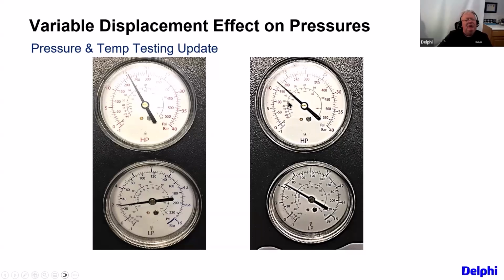In this case, it's because the compressor was put into a lower displacement mode. So normal duty cycle on the right, and high duty cycle on the left. That's why that went higher and the low side went lower. Then when we went to a normal duty cycle, on a hot day, we're at 160 or 170, and about 62 degrees.